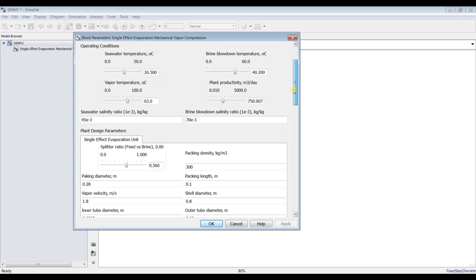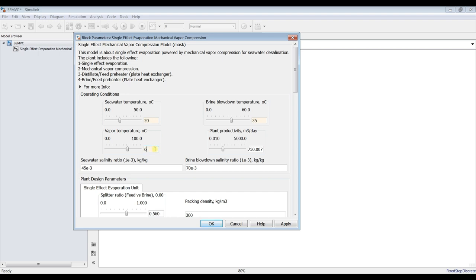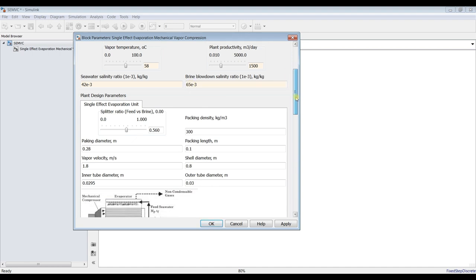Now we have operating conditions. We can assign seawater temperatures, suppose it's around 20 degrees Celsius. Blow down temperature, that's a blow down, brine rejected, let's go for 35. And vapor temperature, normally around 60 degrees Celsius, or let it be 58. And the productivity, suppose I'm going to desalinate around 1500 meter cube per day. These are the salinities, normally around 40, 42. Let's go for 42. And brine blow down salinity because it's a design model, I'm going for 65 kilogram, from 65,000 ppm.